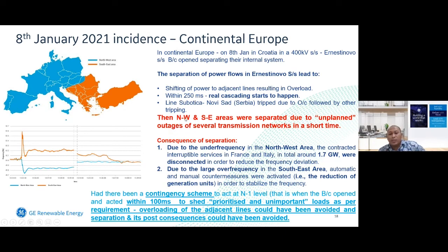Then the northwest and the southeast areas were separated due to unplanned outages of several transmission lines in a short time. As a consequence of this separation, in the northwest area, due to under frequency, contracted interruptible services in France and Italy, in total around 1.7 gigawatts, were disconnected in order to reduce the frequency deviation. In the southeast area, due to a large over frequency, automatic and manual countermeasures were activated, such as the reduction of generation units, in order to stabilize the frequency. With this kind of contingency scheme, it can act within 100 milliseconds to shed prioritized and unimportant load as required. Overloading of the adjacent line could also be avoided, and the separation and its post consequences could also be avoided with this kind of contingency scheme.